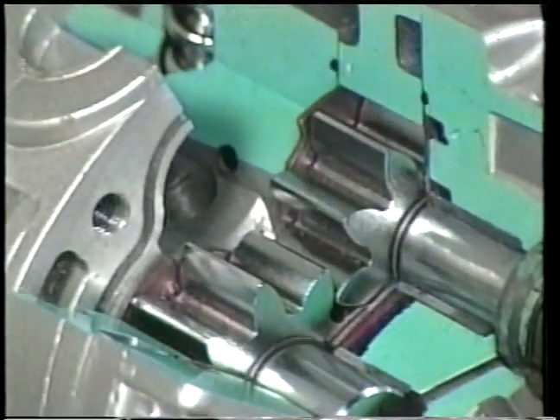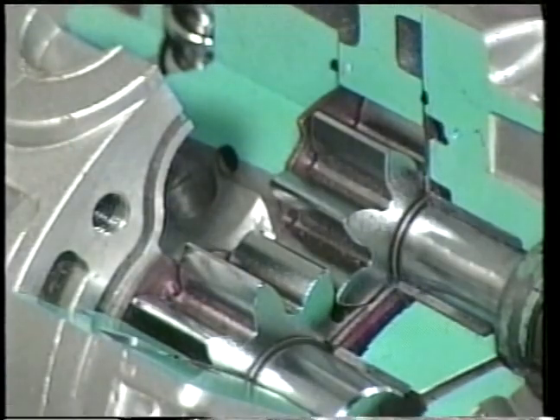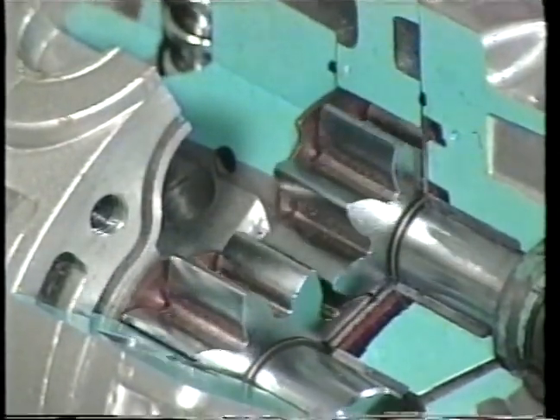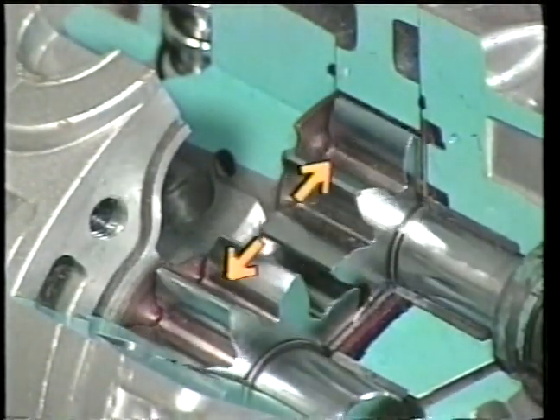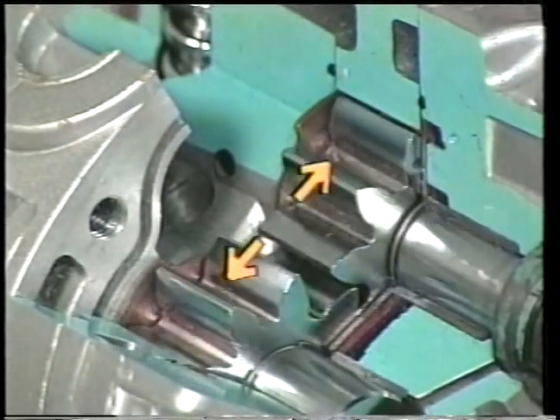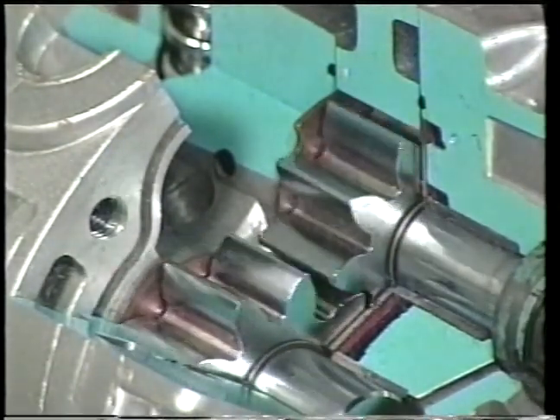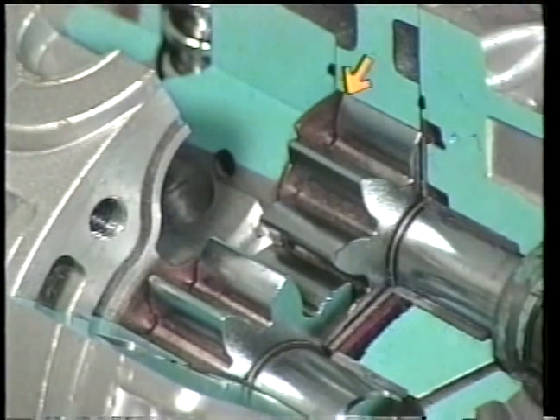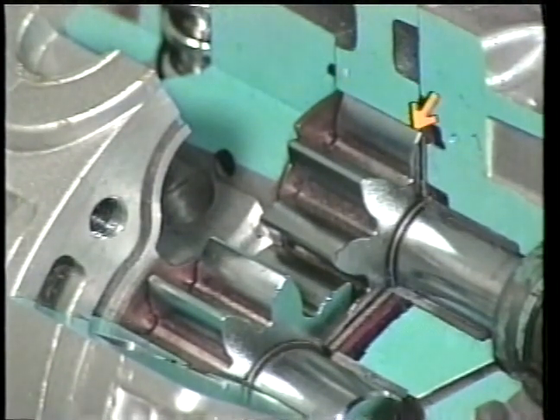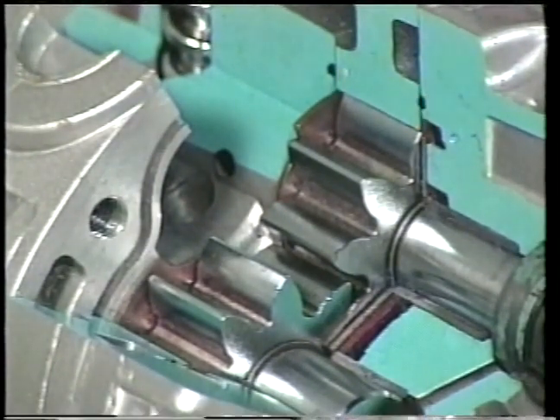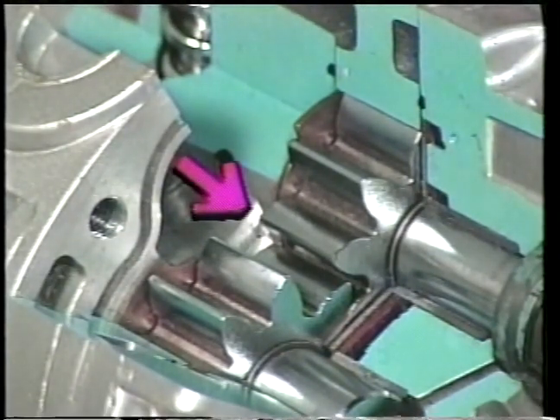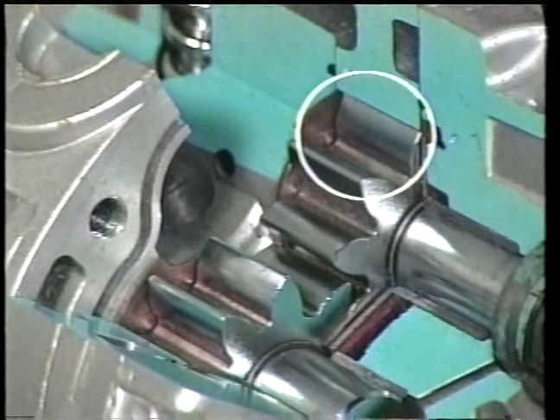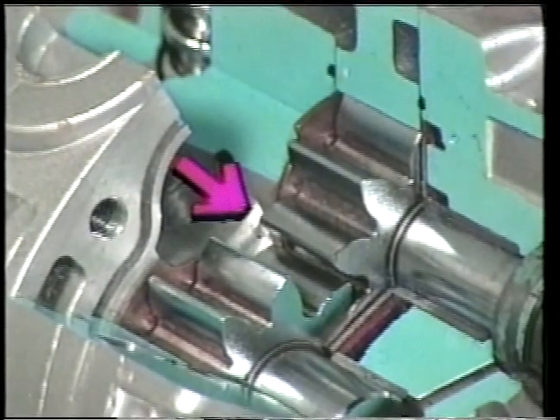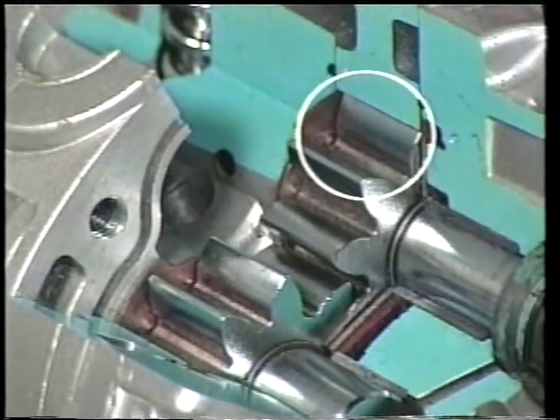Gear-type hydraulic motors operate in a way that is similar to vane-type motors, except pressure at the motor inlet pushes against the sides of the gear teeth, forcing them to rotate. A tight seal between the gears and the housing minimizes fluid leakage past the teeth. The torque created at the motor shaft depends on the pressure at the motor inlet and on the exposed tooth area. The greater the pressure, the greater the torque. And the more exposed tooth area, the greater the torque.